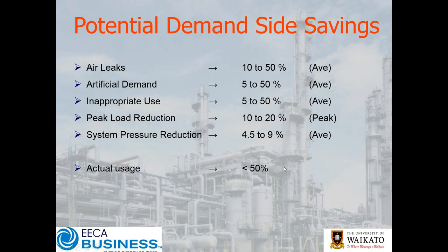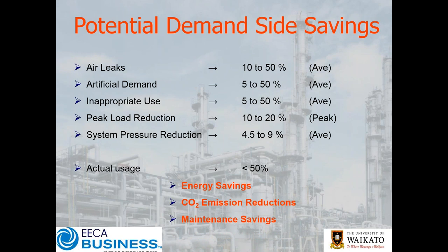When you sum all of this up — and this is really the guts of the presentation today — you will find that on most systems the actual compressed air that needs to be used will be less than 50% of the current usage or demand. In other words, you can probably cut your air demand in half and still preserve all the functionality you need from your system. That's going to deliver energy savings, reduce your emissions, and as you reduce your demand substantially, you start to impact on maintenance costs, especially reducing the number of compressors you could be using.